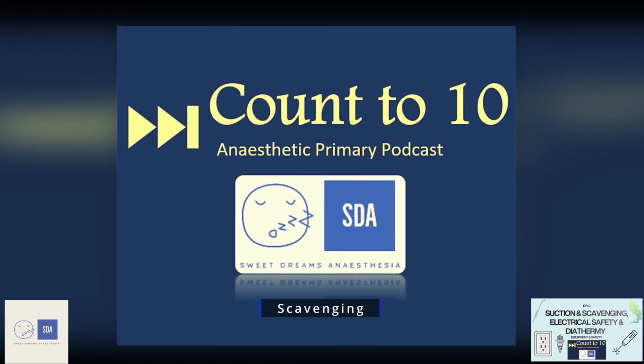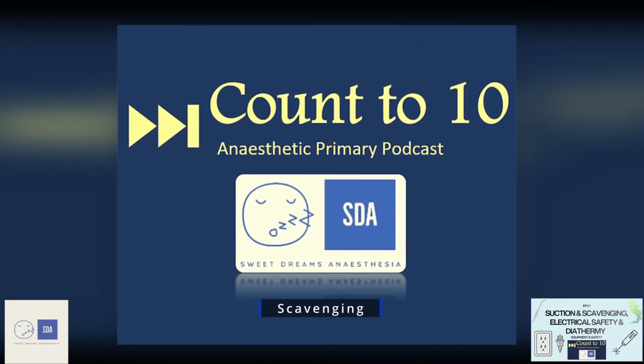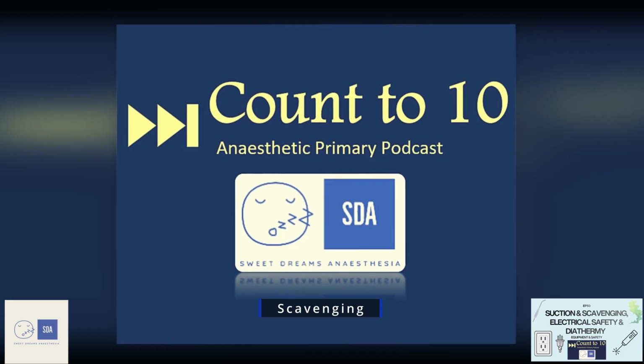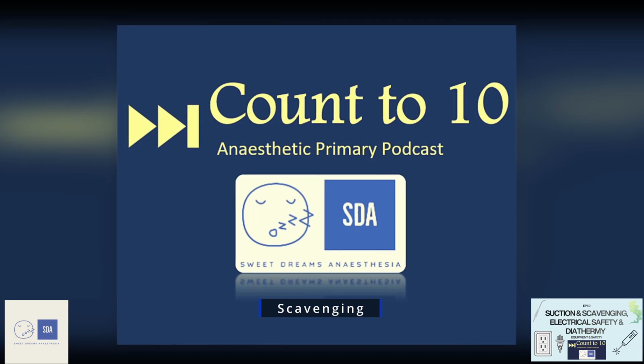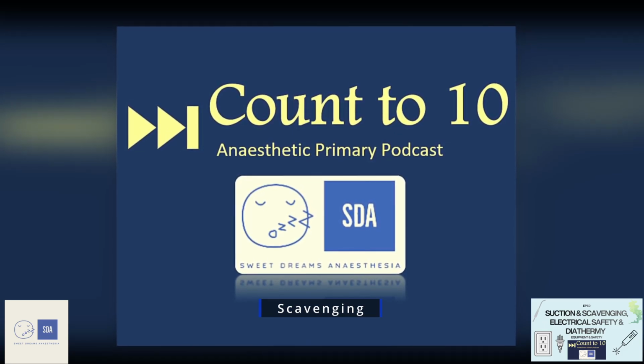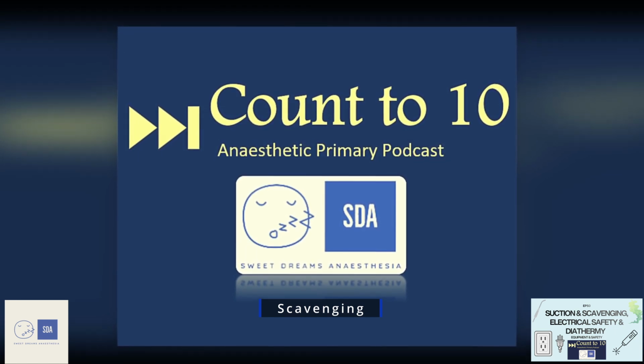In comparison to a passive system, the scavenging interface for these has to be closed, and it's closed because it's relying on that positive pressure generated from the breathing circuit to drive flow. So within these systems, there's a higher risk of barotrauma, and therefore the safety mechanism here is that they have either positive pressure relief valves or negative pressure relief valves. The positive pressure relief valves are set to pop off at greater than a pressure of 5 centimeters of water, and the negative pressure relief valves go off at a pressure of less than negative 0.5 centimeters of water.